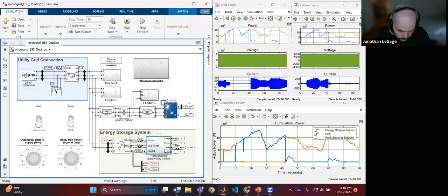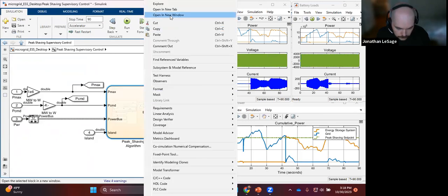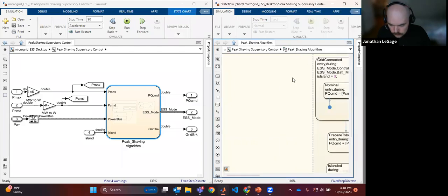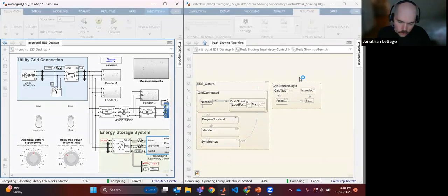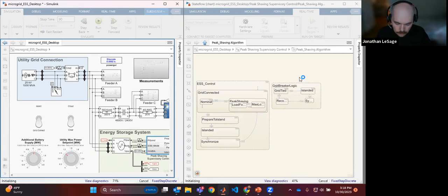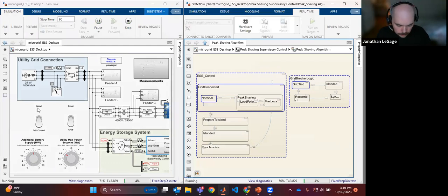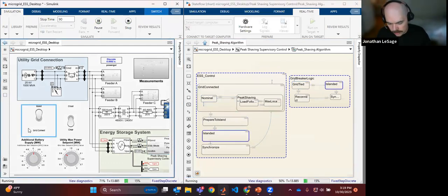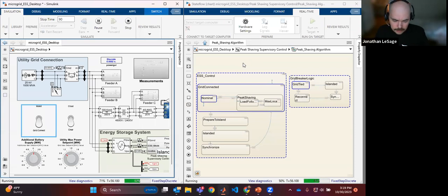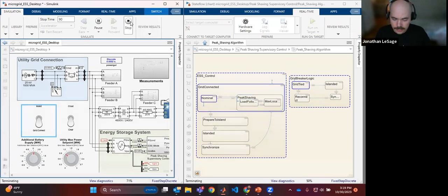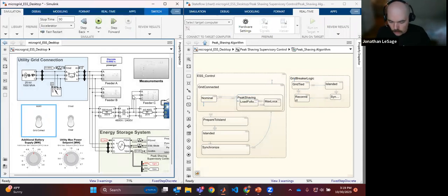I can open the control chart as a separate window. We'll run it one more time to study the performance of the higher-level control. We're grid connected — I can throw the island command, see that it's now islanded, and when I hit reconnect you'll see it's temporarily unsynchronized, and then once we've resynced with the main grid we go back into grid-connected mode. This can be deployed for real-time simulation and test through Speedgoat or Opal-RT systems for hardware-in-the-loop validation.